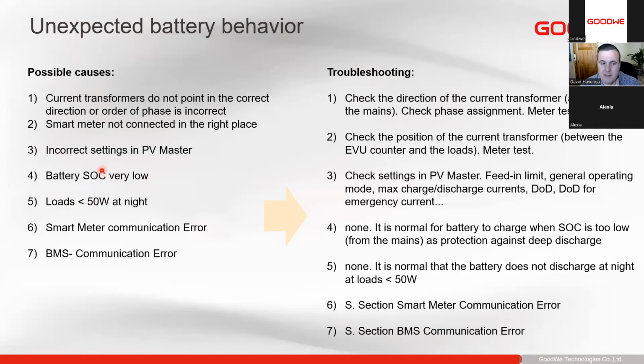If the battery SOC is very low, especially in European countries where you have a lot of snow or bad weather for a very long period of time, when the batteries get to a very, very low percentage, it will automatically recover charge and will charge the batteries up to a safe level, and then it will continue normal operation. So that is quite normal to see.